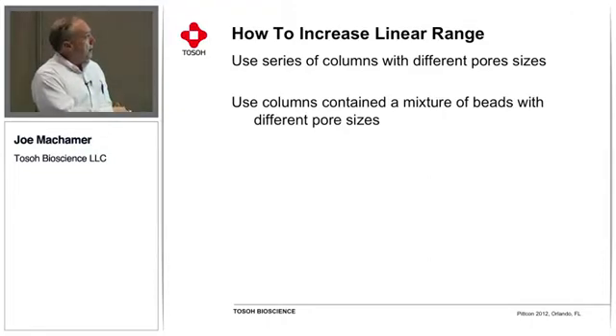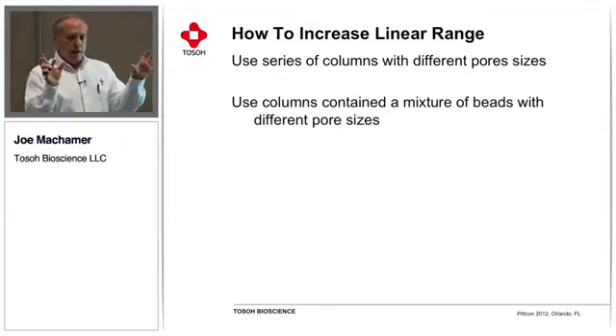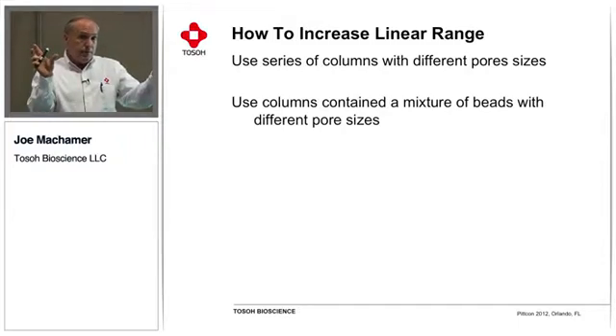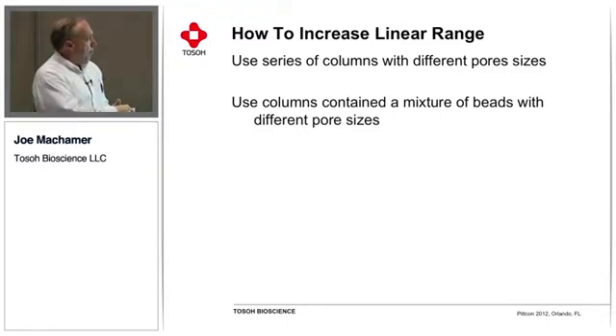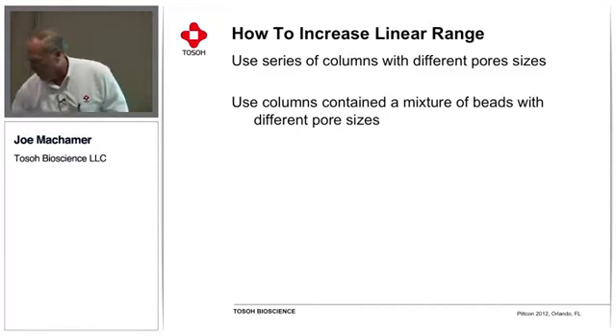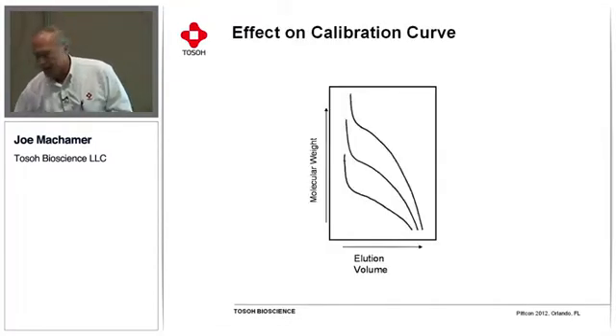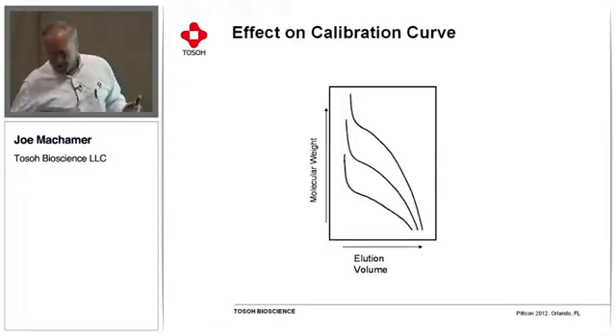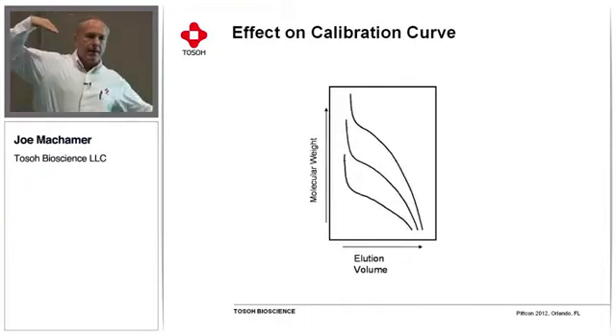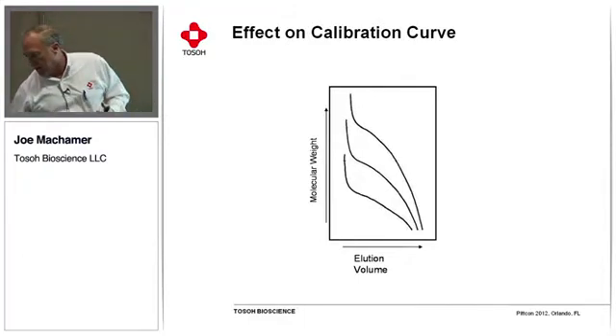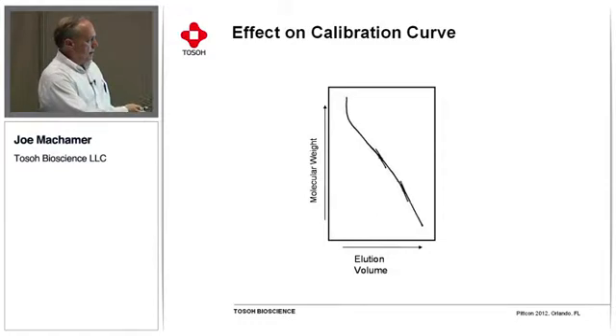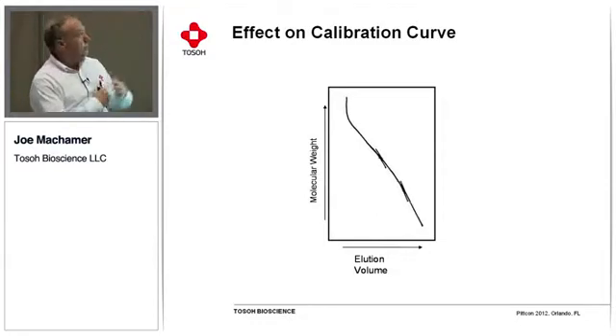That's one approach. Another approach has been to take the material that would be in those individual columns and mix them together, creating a mixed bed column, and then connect a series of those types of materials to each other for a mixed bed. And the idea is that you would take these individual calibration curves, and by either hooking them together in series or mixing the beads together and then packing the column, you would create a calibration curve that had a wider linear range.